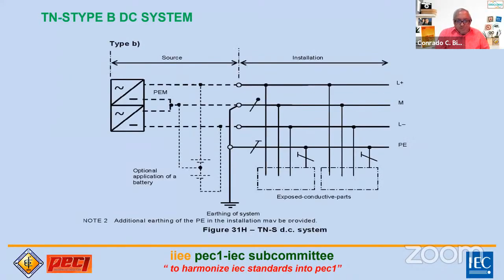Then we have what's called Type B, with a PEM. PEM is like a PEN, but it's called the midpoint, Protective Earth Midpoint. There's a midpoint between the two DC sources, positive and negative, connected there. That's called PEM. He used this as the midpoint connection. Some loads may need positive, others negative, so it comes from the midpoint. This is how the installation is done and how the protective earth is connected to the equipment, grounded here, earthed here, then connected to the PEM.